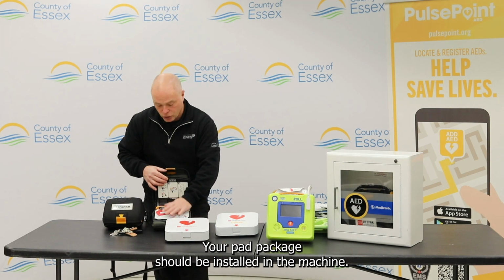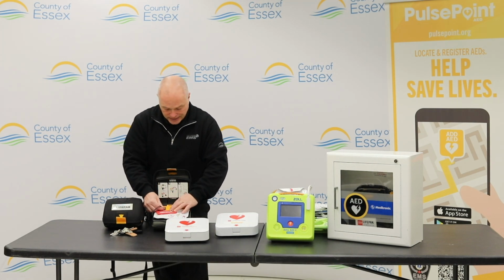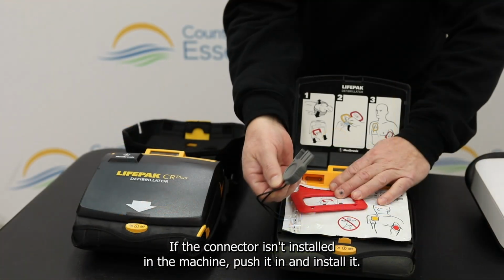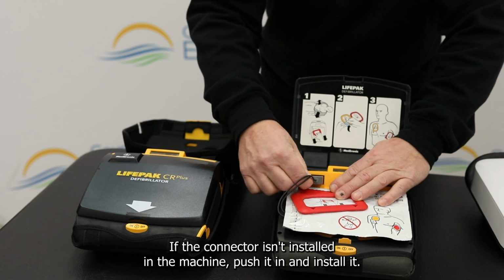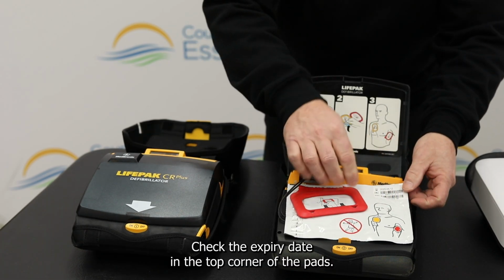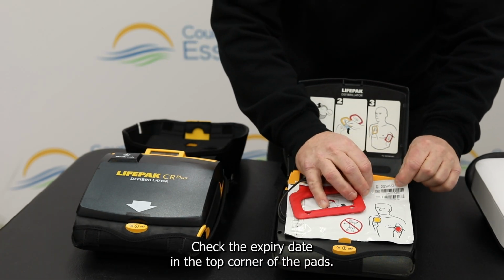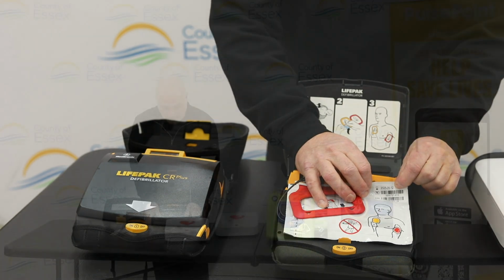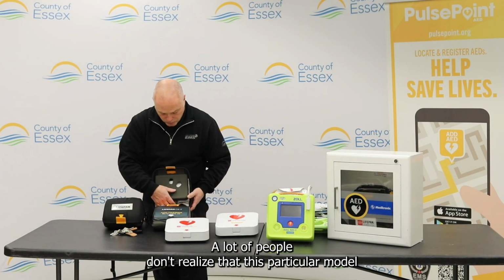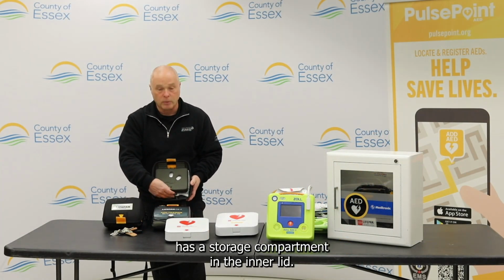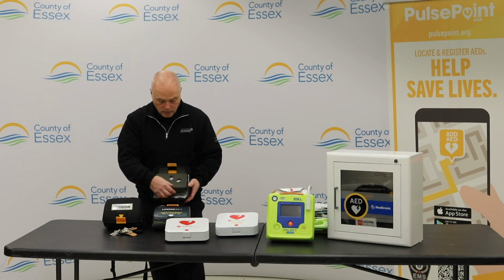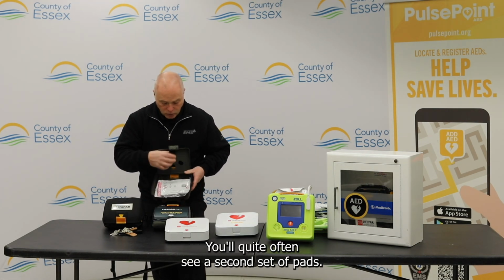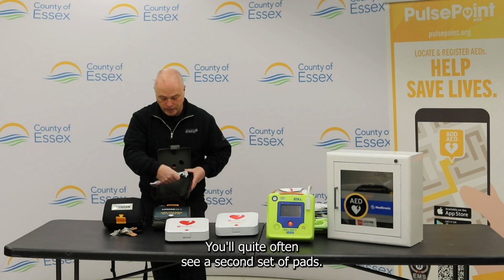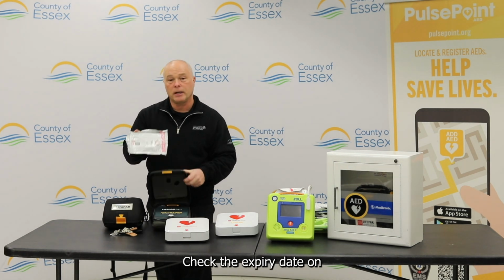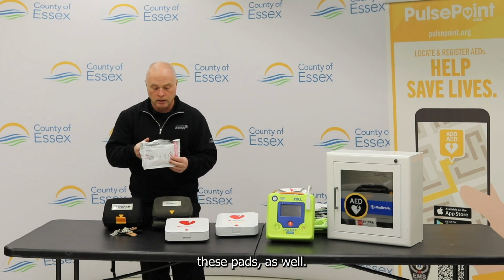Your pad package should be installed in the machine. If the connector isn't installed in the machine, push it in and install it. Check the expiry date in the top corner of the pads. A lot of people don't realize that this particular model has a storage compartment in the inner lid. Lift this cover, you'll quite often see a second set of pads. Check the expiry date on these pads as well.